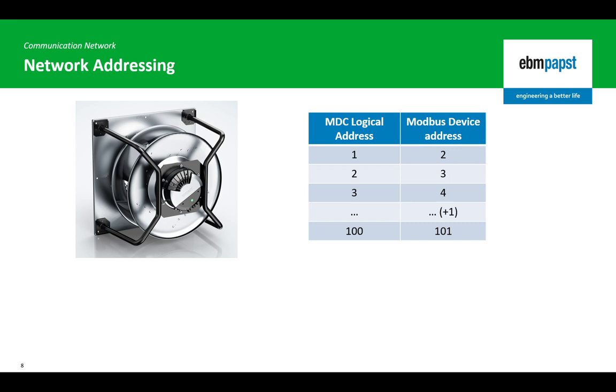This distinction is important for two reasons. Firstly, the MDC has been programmed to initialize the network with the first fan in the array being assigned Modbus device address 2. For every additional fan in the array, the Modbus device address increases by 1, up to 101 for the 100th fan in the array.